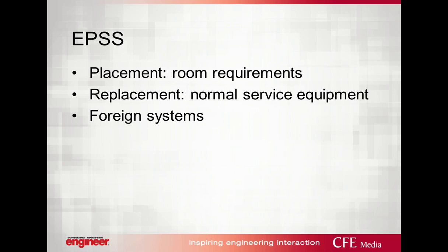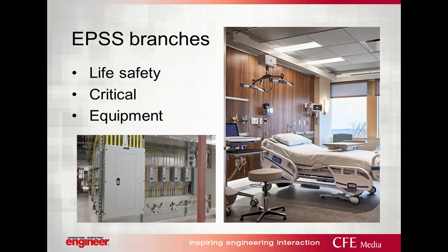If we're replacing transfer switches or equipment, we have this tendency to want to put them back in the same location they were. That makes sense if it's a legal location, but if your building's more than 30, 40 years old, it's very likely everything's combined into one space. I want designers to pay very careful attention to this and make sure that when you're replacing EPSS equipment, it's going into a legal location and not just its previous location. And that also means coordinating with the foreign systems that are likely to exist, such as ductwork and plumbing.